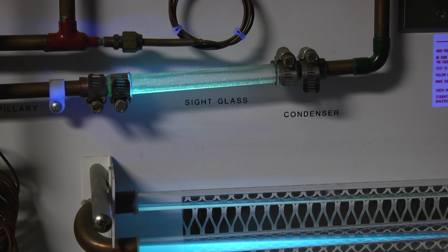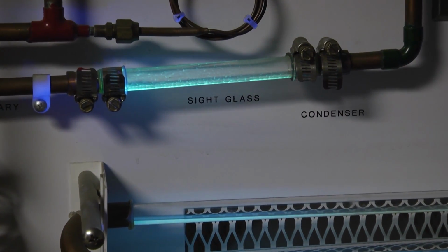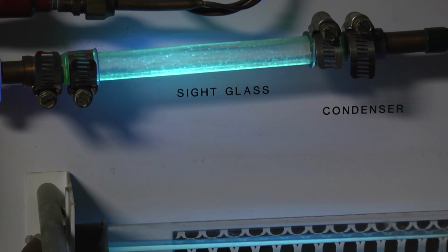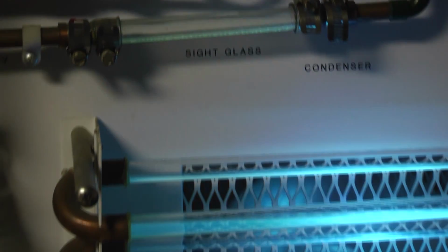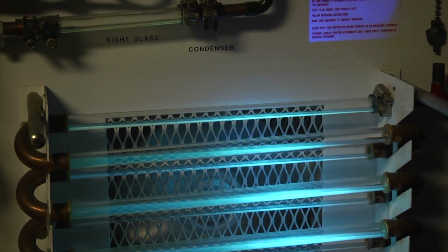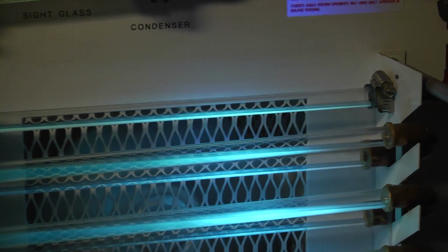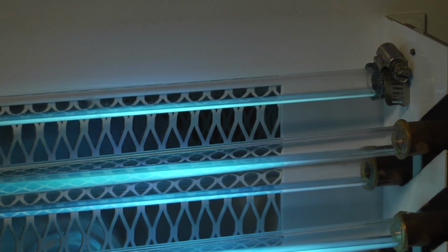The only thing traveling through the discharge line is small droplets of refrigerant oil that leave through the compressor. They go through the discharge line, and now they enter into our condenser at this first row. And as you can see, when the refrigerant first enters, it's almost invisible. That's because entering the condenser, we have 100% superheated refrigerant vapor.